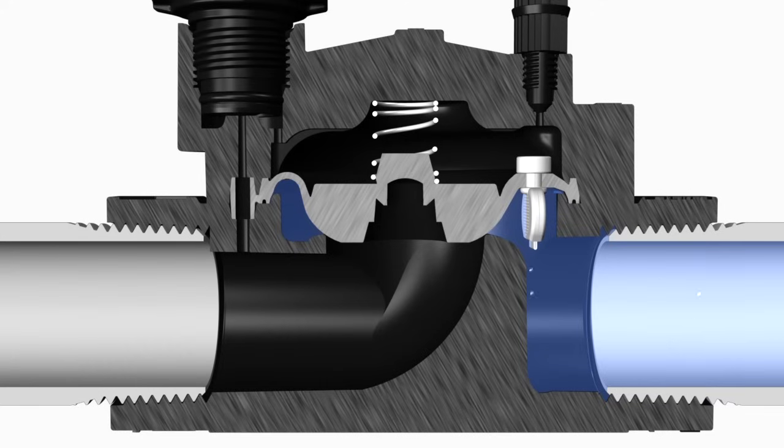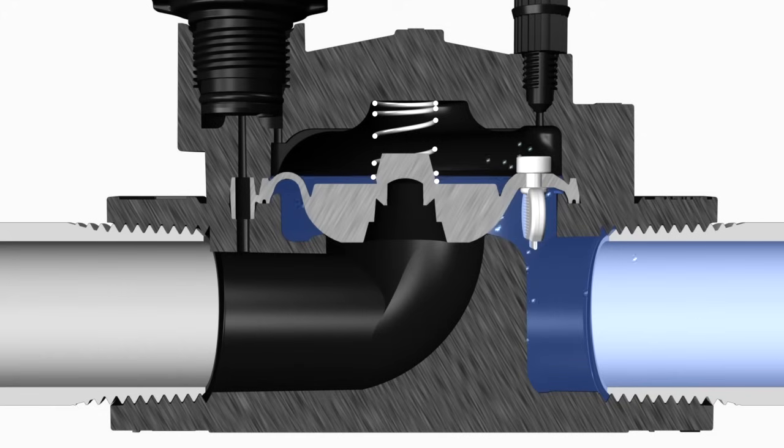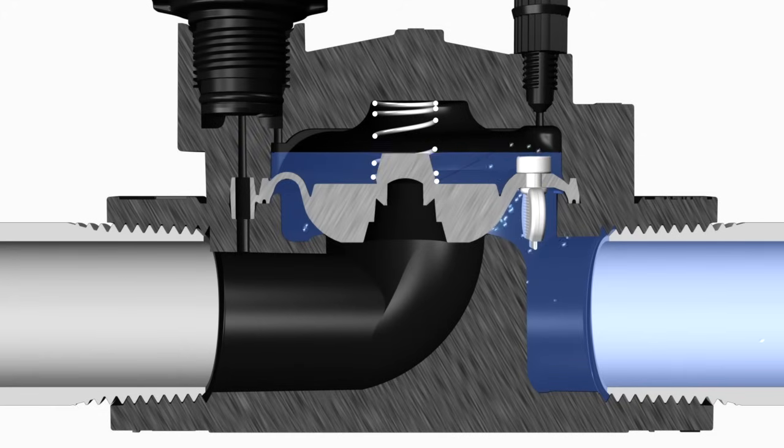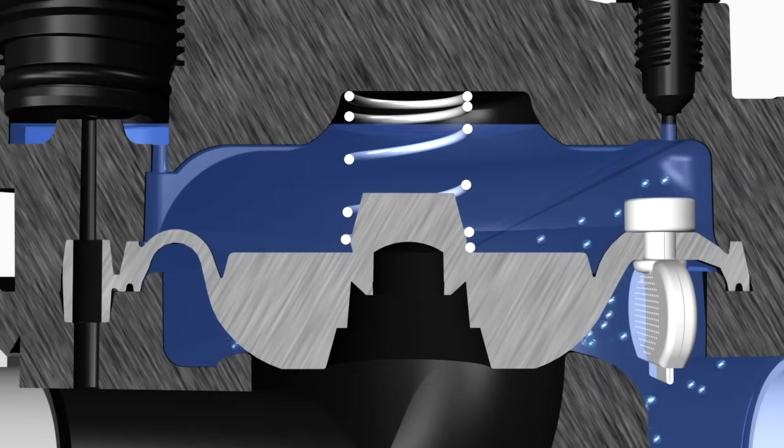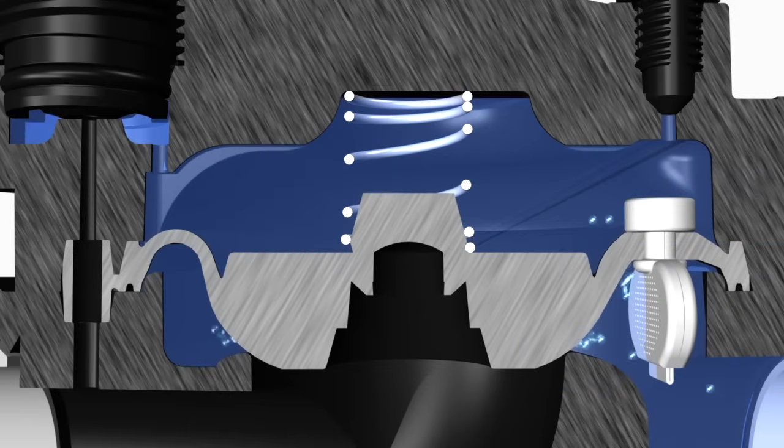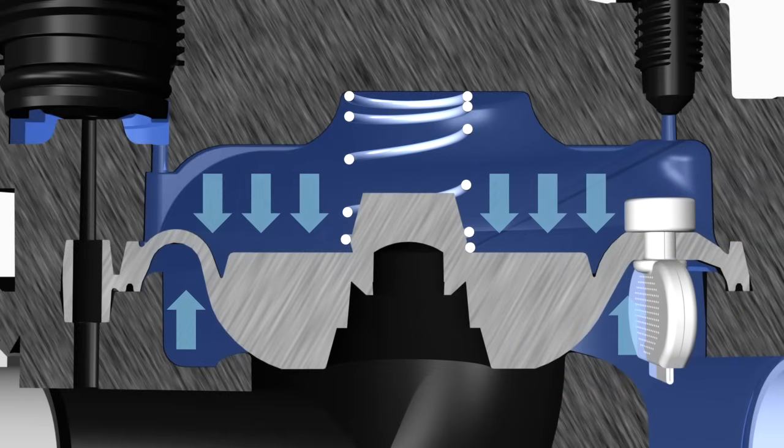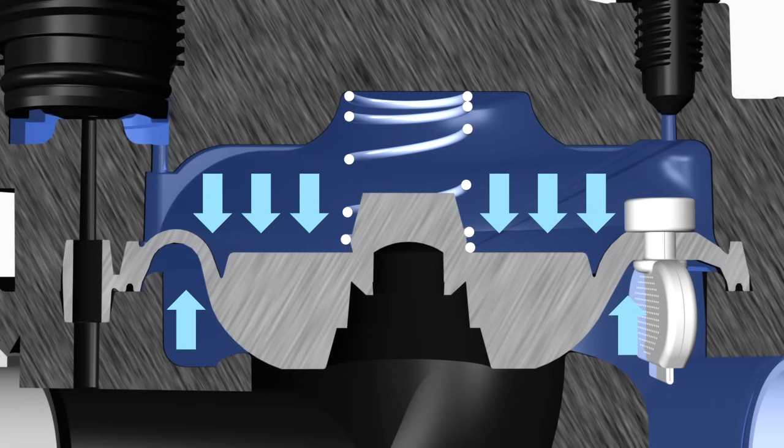Water naturally flows into the inlet side of the valve, which is most often located on the side opposite the solenoid. Water fills the bonnet chamber above the diaphragm via the pilot flow filter, and the force of this water pressing down on the diaphragm holds the diaphragm in place.